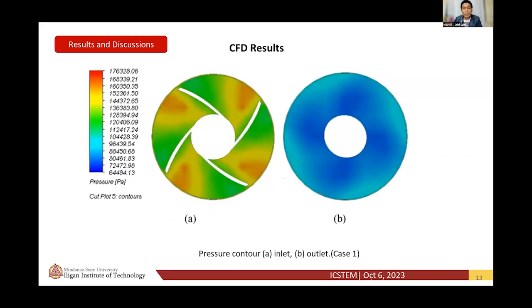So these are the planes. We cut a plane between the runner blades and the guide vane. As you can see, the pressure concentration is near between the tip of the blades and the draft tube. The maximum estimated pressure here is from 168 kPa to 176. And in B, that is the outlet of the runner blades. Since it is a low pressure side, the maximum pressure value is 96 kPa.